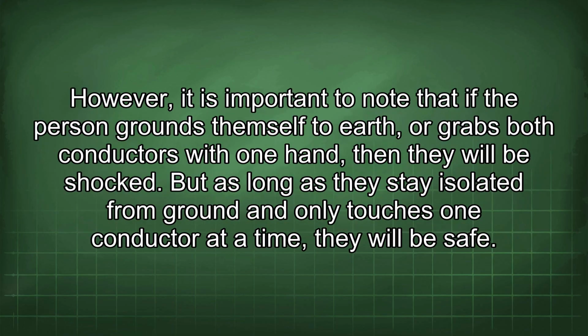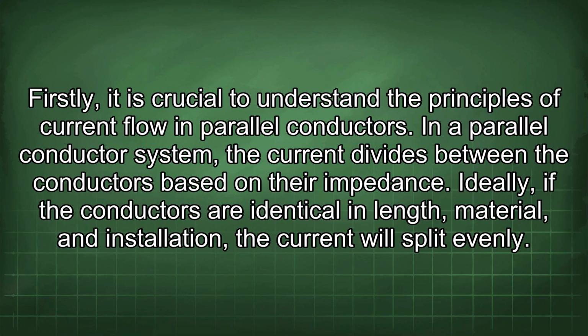However, it is important to note that if the person grounds themselves to earth, or grabs both conductors with one hand, then they will be shocked. But as long as they stay isolated from ground and only touch one conductor at a time, they will be safe. Firstly, it is crucial to understand the principles of current flow in parallel conductors.